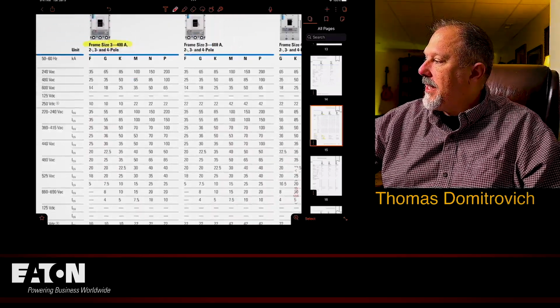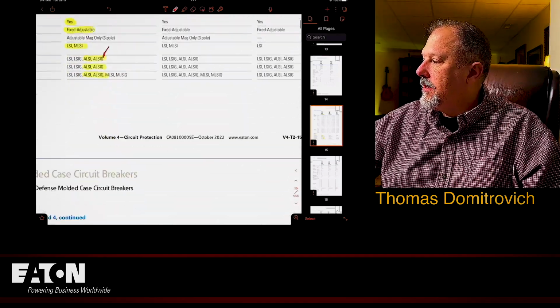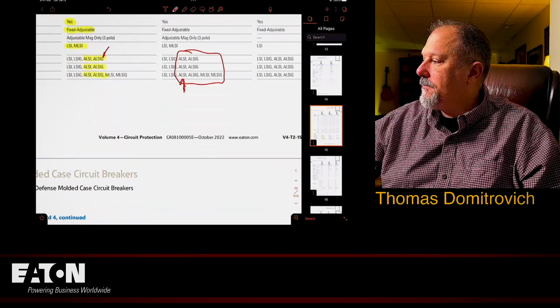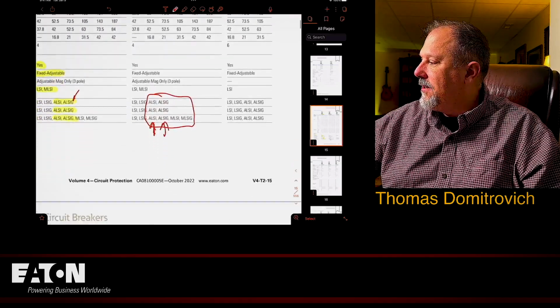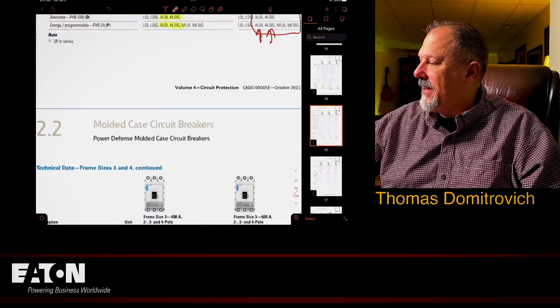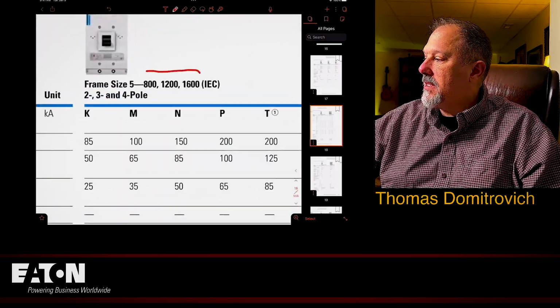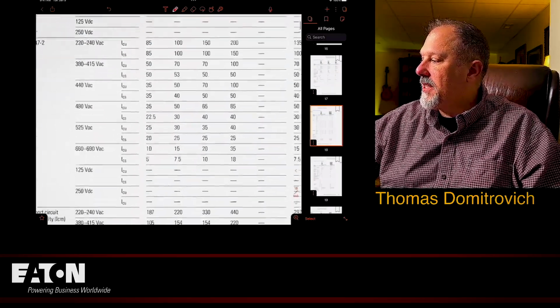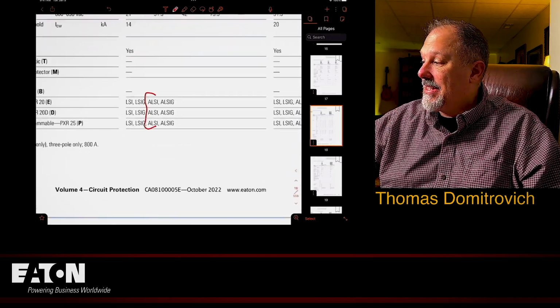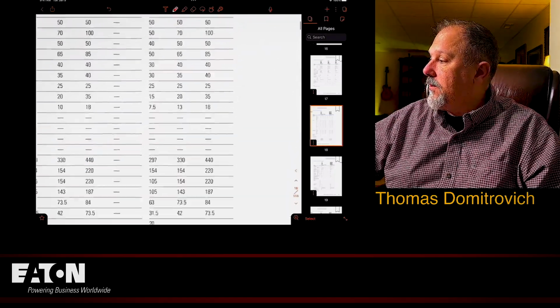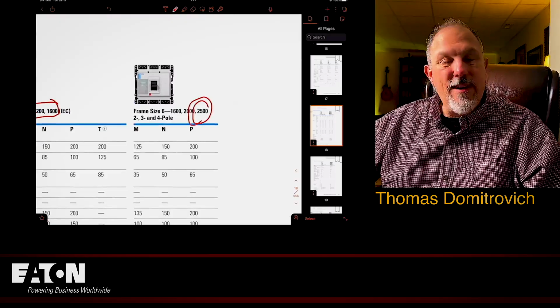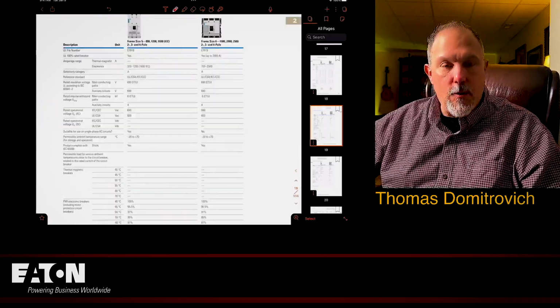Because look, frame size up to 600 amps. Looky, ALSI right there. This is 800 amps. Look, ALSI. Love it. There we go. This up to 1600 amps. Frame size 5. ALSI. ALSI on this one. And what does this go up to? 2500 amps.